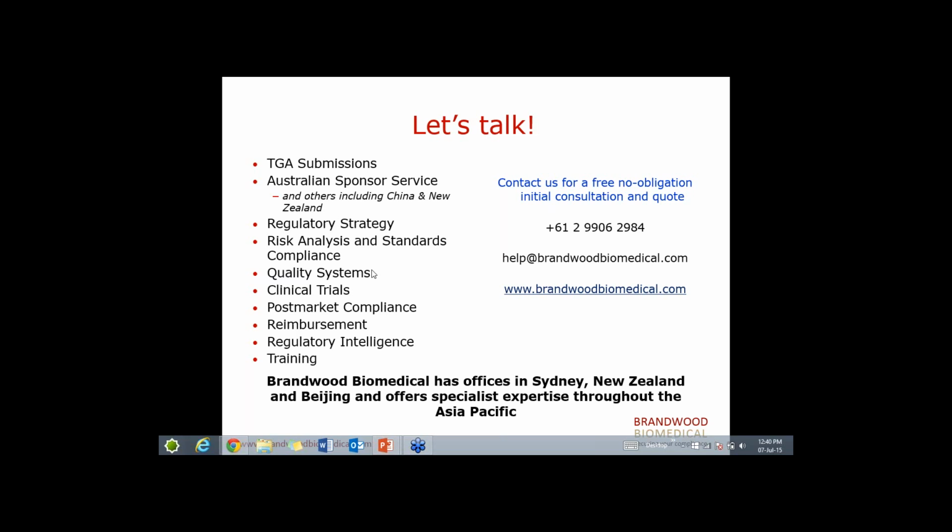If you go through TGA, you have to go through two departments: conformity assessment, and once you've got that, devices. But if you've got an EC certificate, you can go straight into your device application. So it is much more fast track, but in saying that, it could take from a few weeks to a few months, depending on the resources. Also, if the application is selected for an audit, there are additional questions asked by TGA, and that can add to the time. But compared to TGA conformity assessment, it is a much quicker process.